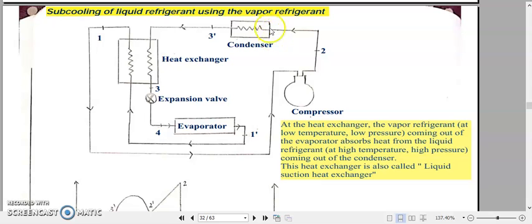But at this condenser, no pressure is reduced. So the liquid refrigerant coming out of the condenser will be at a somewhat high temperature, and at a very high pressure also. It is this high pressure, high temperature liquid refrigerant which flows from 3 dash, enters the heat exchanger and moves on to the expansion valve at 3. This high temperature, high pressure liquid refrigerant flowing from 3 dash to 3 through the heat exchanger can very well reject heat to the vapor form of the refrigerant, which is at very low pressure and low temperature, coming out from 1 dash and moving towards the heat exchanger.